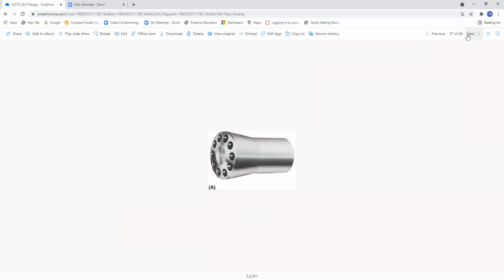Here we have a distributor, and basically this is going to be mounted on the outlets of the metering device, in this case the thermal expansion valve. With this distributor, we are going to be hooking up capillary lines, and the capillary lines will tie into the individual circuits of the coil. In this case, we have a lot of circuits on the evaporator coil with this distributor. Very simple device. There's technically no maintenance you're ever going to have to do with these. They work extremely well.